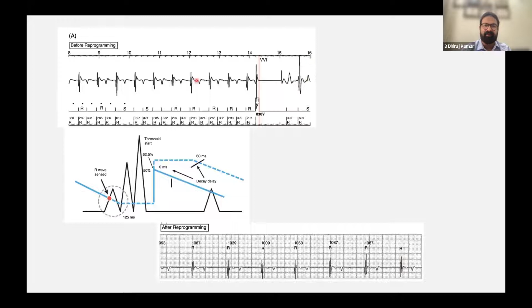Now, this is how the algorithm of a dual chamber ICD works. The first step that a dual chamber ICD does whenever it senses a high rate event is to compare what is happening at an atrial channel and what is happening at a ventricular channel. If the ventricular rate of the event is higher than the atrial rate, it knows that the problem lies in the ventricular chamber, and therefore it classifies it as VT and delivers the therapy. If the atrial rate is higher than the ventricular rate, it is likely to be an atrial arrhythmia which is getting conducted at a variable rate to the ventricles.